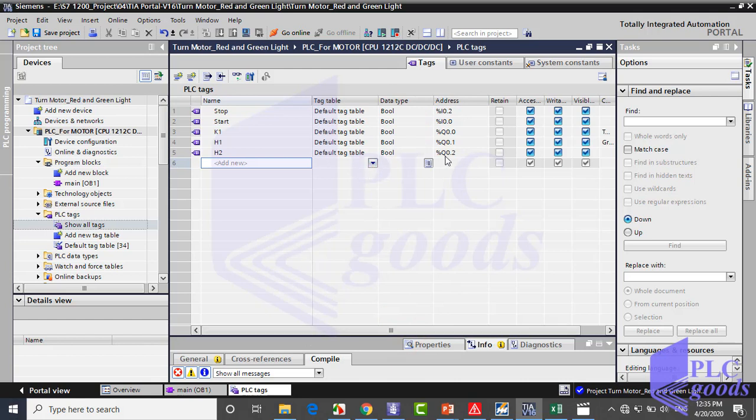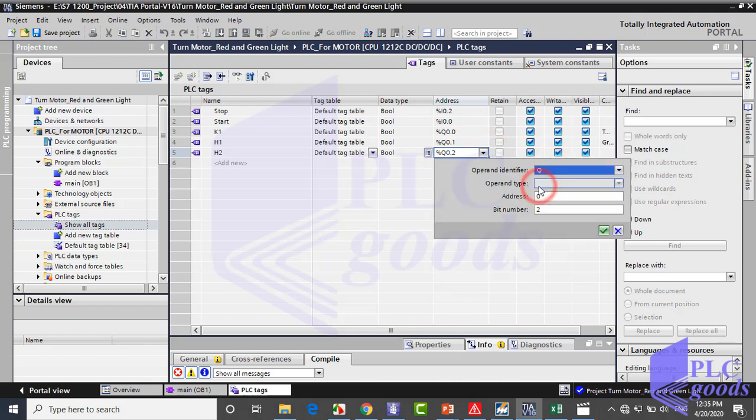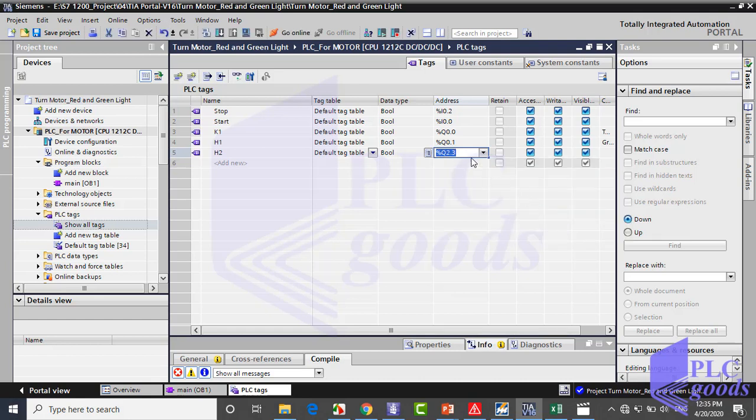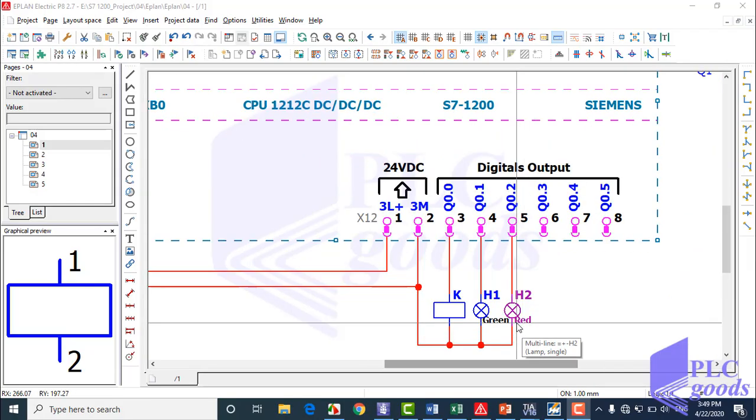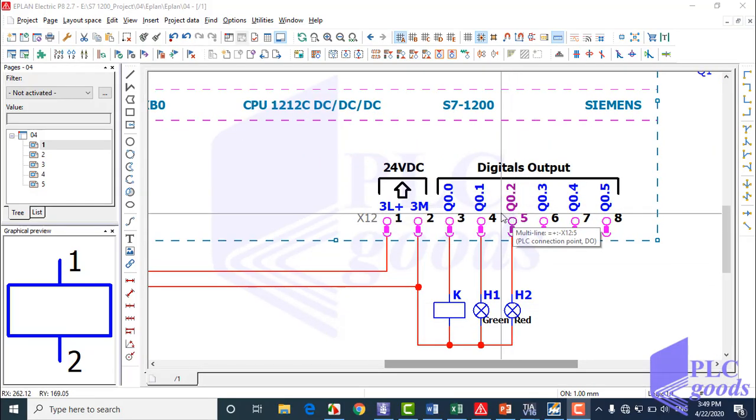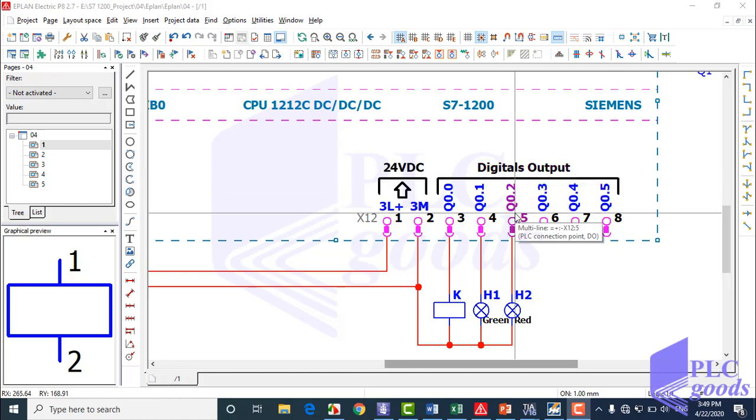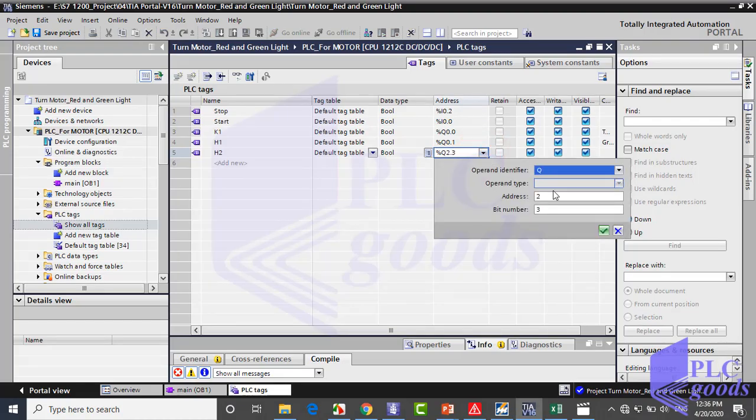As you see, in the address column we can change the address. Here we must determine the address refers to PLC input, output, or its memory. Then determine byte number and its bit number. See here, my red lamp with h2 tag is connected to q0.2, so I define this address for h2 tag.